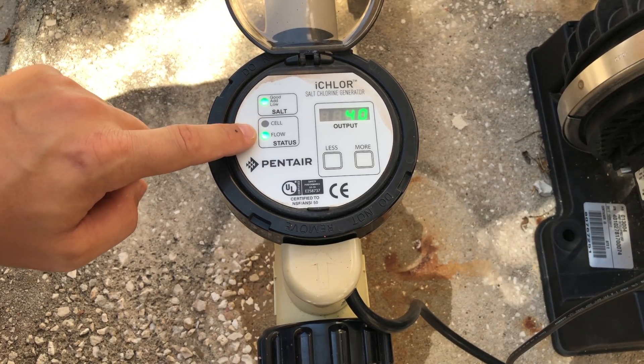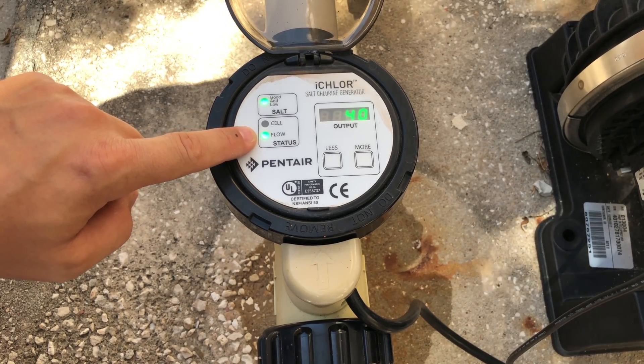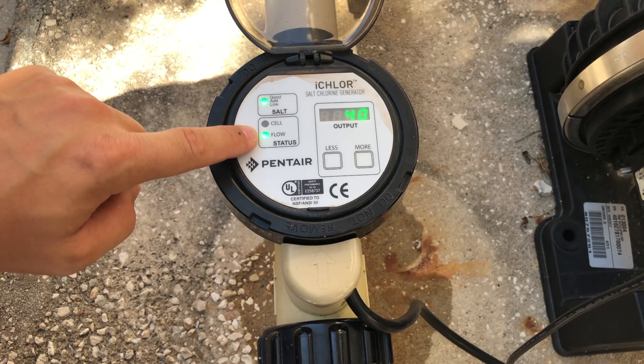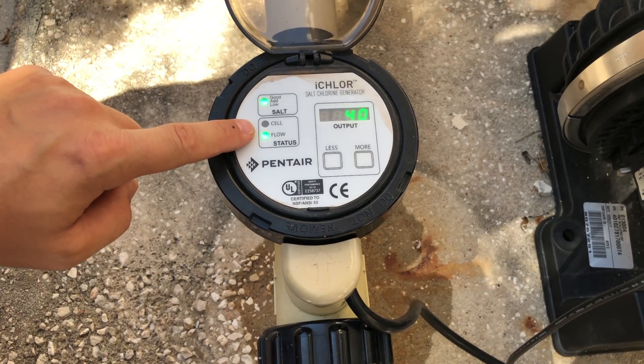The temperature sensor is tied into the flow switch, so you're actually replacing the flow switch as well. In regards to the flow switch — right now it's flickering green, which means it's communicating with an automation system, an IntelliFlo, or IntelliPro pump. This one is talking to an IntelliPro right now.